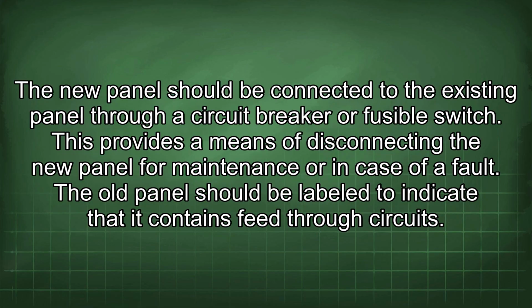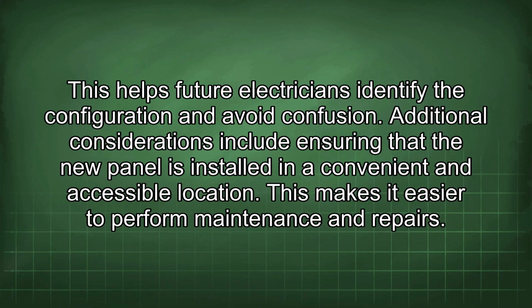The new panel should be connected to the existing panel through a circuit breaker or fusible switch. This provides a means of disconnecting the new panel for maintenance or in case of a fault. The old panel should be labeled to indicate that it contains feed-through circuits. This helps future electricians identify the configuration and avoid confusion.